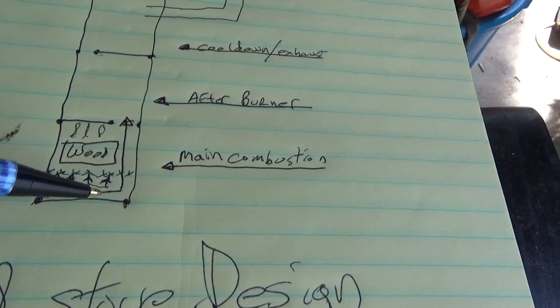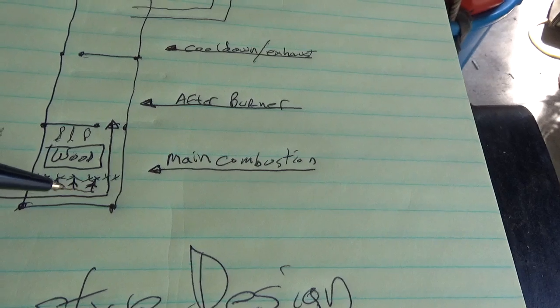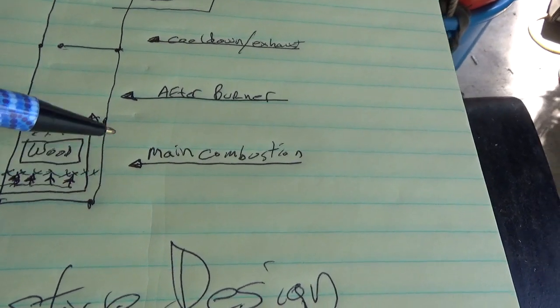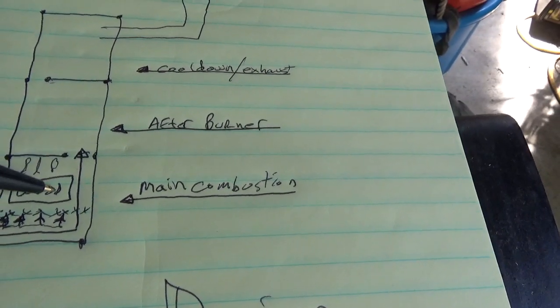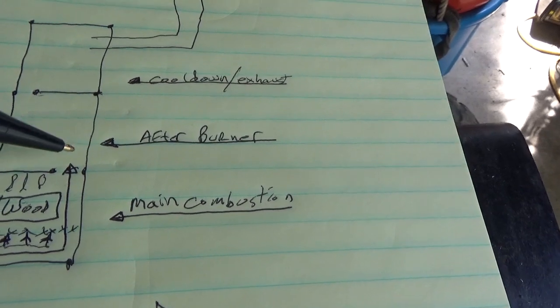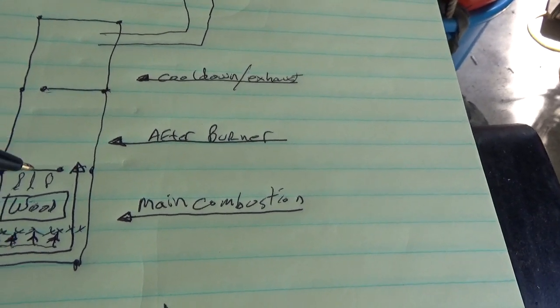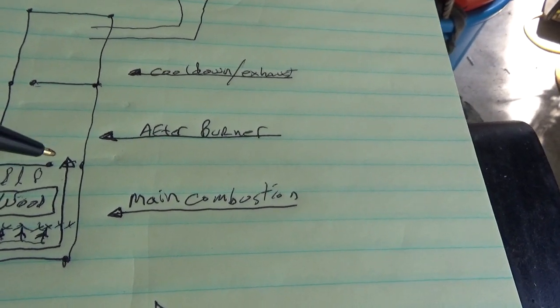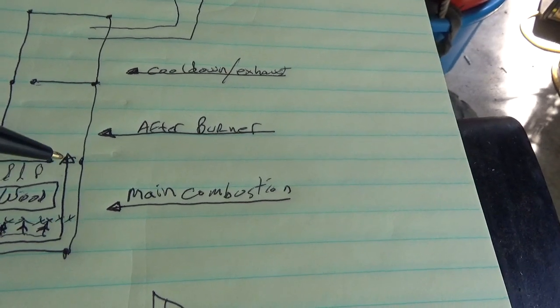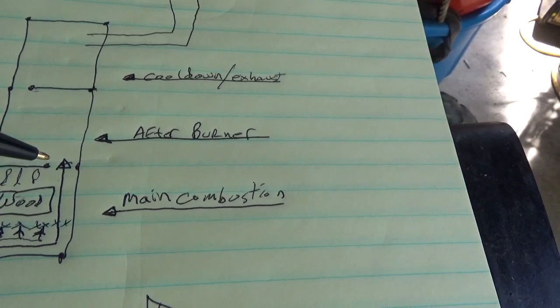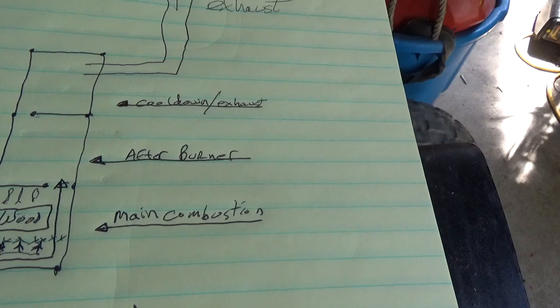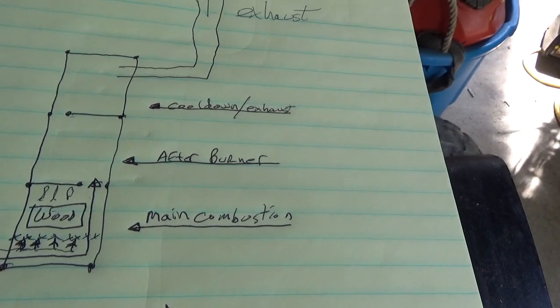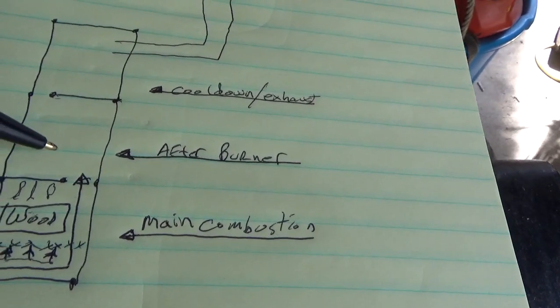In addition, what you want is an extra air supply kind of in a pipe so that it warms up with all this, and it's introduced after the combustion chamber. You see that baffle right there, so you introduce fresh air that's already hot. The air has to be hot because if not, what you do is you actually cool off the gases there.